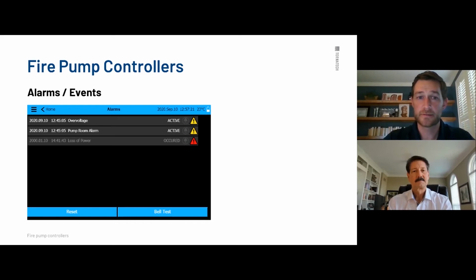If it was, I would imagine it's a yellow case for under voltage here because it's not to a critical point. It must be within some sort of tolerance, because if it gets too far out of tolerance, it would be a critical alarm. But you can also see here where it says loss of power, and next to loss of power it says it occurred, but that's a critical alarm. So you can see it's red.